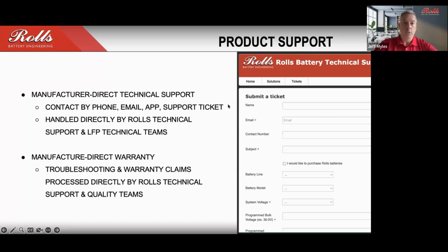Once those batteries are assembled in a stack, then you would start with your terminal connections. The bus bars that are provided are obviously sized to go from one battery to the next. You're also going to have ground cables that are supplied. On the base of the unit, there are two spots for ground connections. One of those is going to connect to your main ground, and the other will be connected to the first battery in the stack. Each of the batteries has two spots to mount a ground connection. The lower one is connected to either the battery below it or to the base, and the one on the top is connected to the next battery in the stack. They're all obviously sized appropriately to complete those connections. Basically, you just follow that process as you move up the stack.